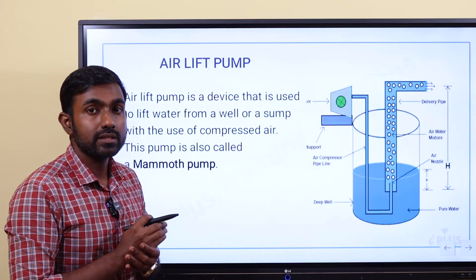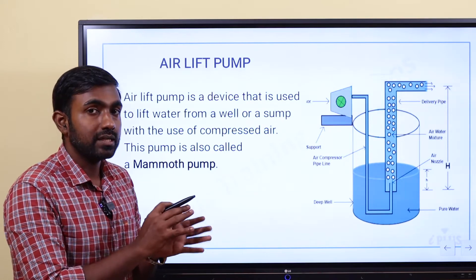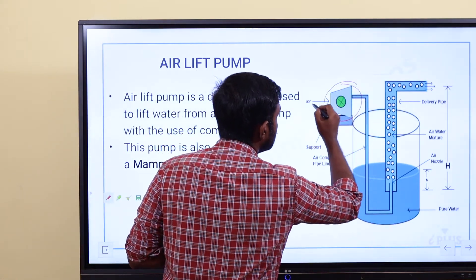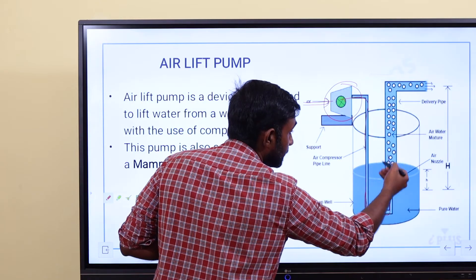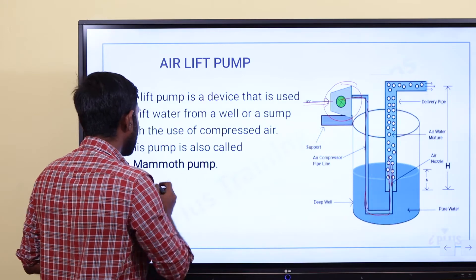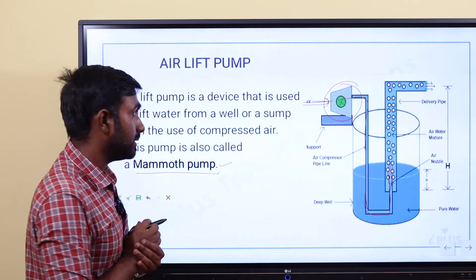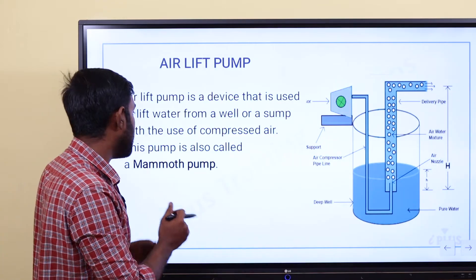The air lift pump is used to lift water from a well or a sump using compressed air. We put a compressor — the compressor pushes compressed air into the pump, creating an air and water mixture that lifts the water up. This pump is also called a mammoth pump.